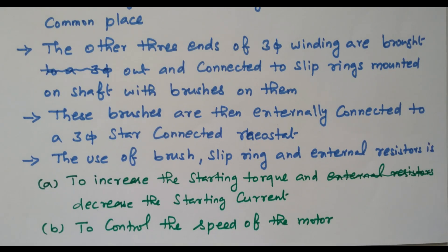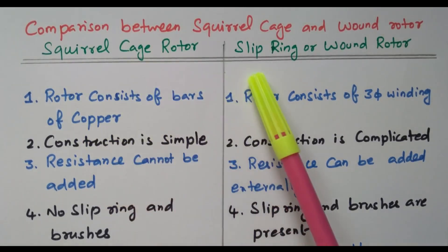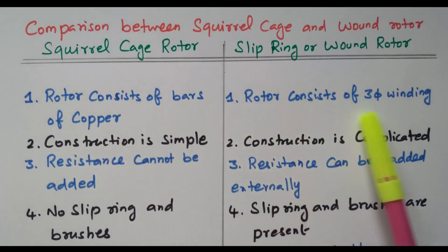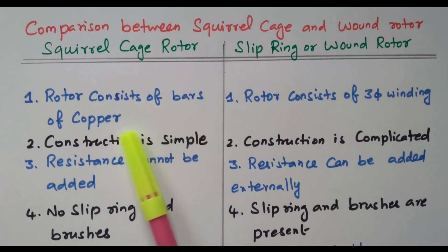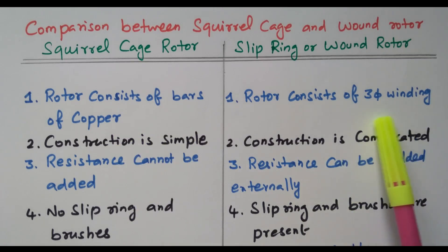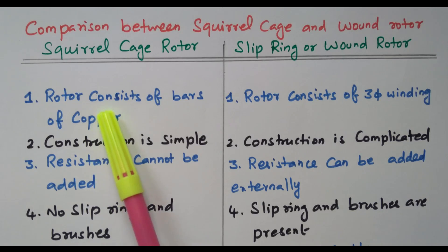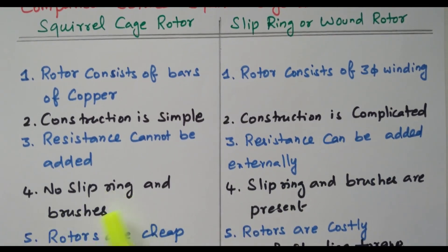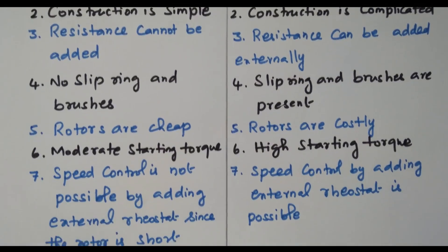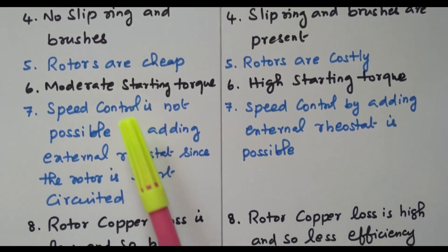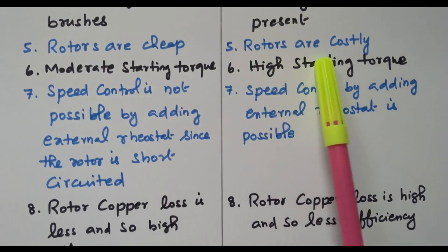Now we will compare the squirrel cage rotor and the slip ring or phase wound rotor. In the squirrel cage rotor, the rotor consists of copper bars, whereas in the slip ring rotor, a three-phase winding is available. The construction of the squirrel cage rotor is simple — copper bars are placed during construction with no alteration needed — but the slip ring rotor construction is complicated because three-phase winding must be placed. In the squirrel cage rotor, external resistance cannot be added; in the slip ring rotor, external resistance can be added. The squirrel cage rotor has no slip ring and brush; the slip ring rotor requires both, and is therefore more costly.